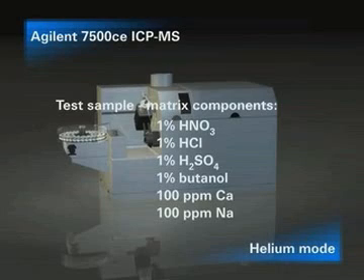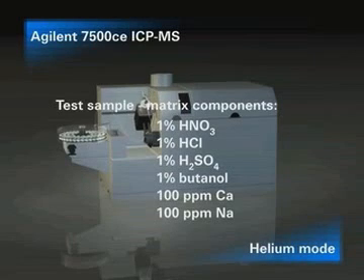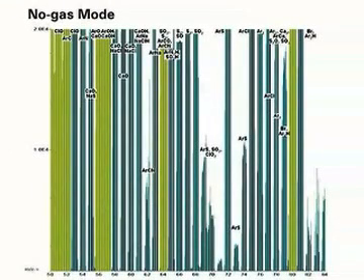To illustrate the interference removal power of the helium mode, a very challenging sample matrix containing these components was analyzed. Spectra were obtained for the mid-mass range where most polyatomic interferences occur. This spectrum shows the matrix interferences that occur in normal ICP-MS. This spectrum was acquired in normal mode — that is, with no gas added to the cell. Almost every analyte in this mass range suffers severe polyatomic overlaps, making quantification impossible at trace levels.